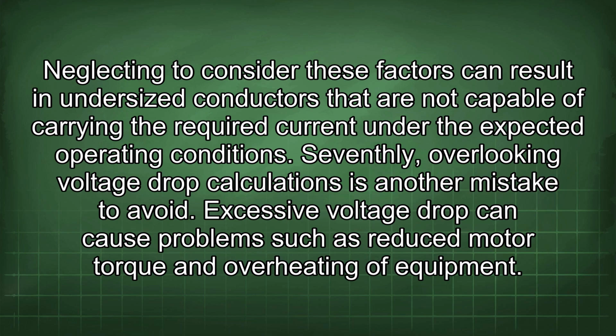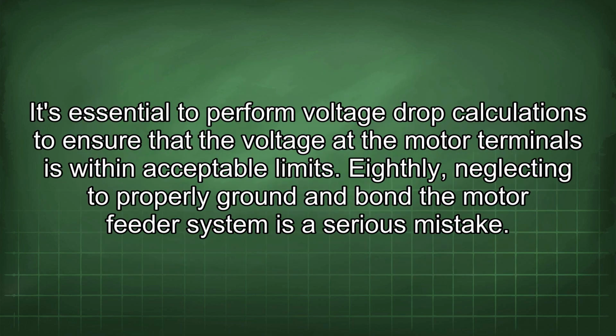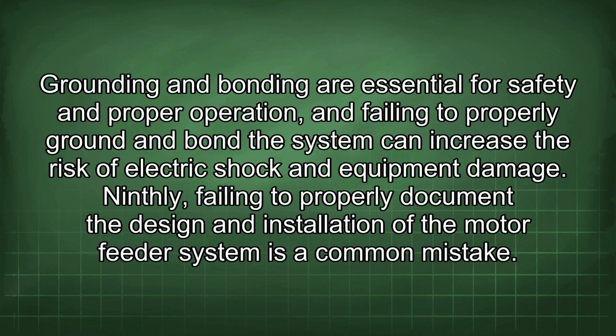Excessive voltage drop can cause problems such as reduced motor torque and overheating of equipment. It's essential to perform voltage drop calculations to ensure that the voltage at the motor terminals is within acceptable limits. Eighthly, neglecting to properly ground and bond the motor feeder system is a serious mistake. Grounding and bonding are essential for safety and proper operation, and failing to properly ground and bond the system can increase the risk of electric shock and equipment damage.